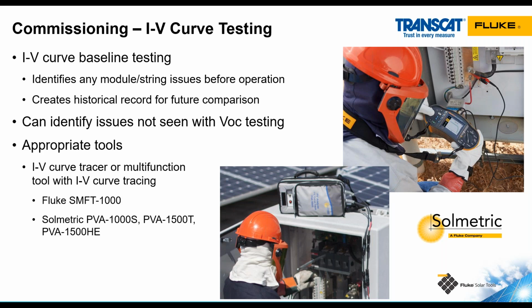At Fluke, we have 3 models of IV curve tracers. The SMFT 1000 will test up to 1,000 volts and 20 amps. We actually have 2 versions of the Solmetric product, the PVA 1500T2 and the PVA 1500HE2. Those will both test up to 1,500 volts and 30 amps. And the big difference between the 3 models is how they work with high efficiency modules.